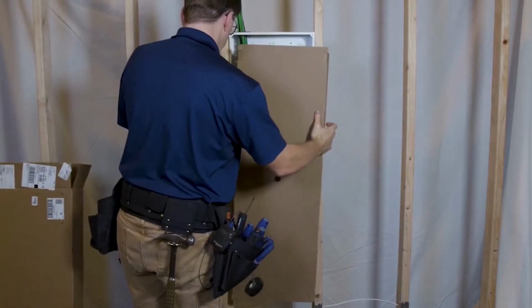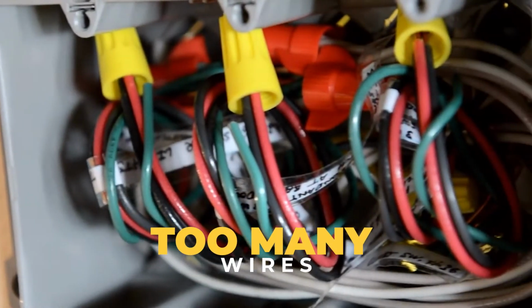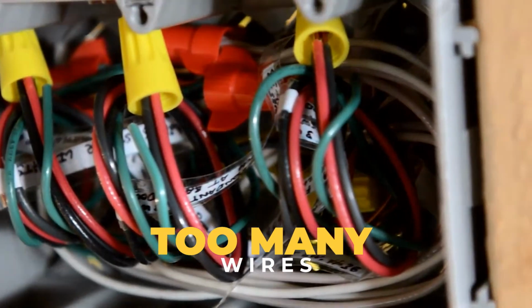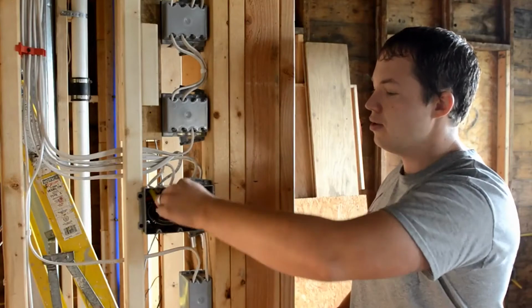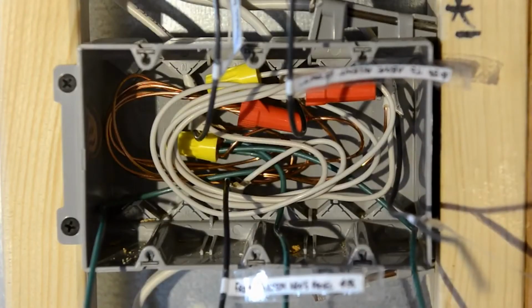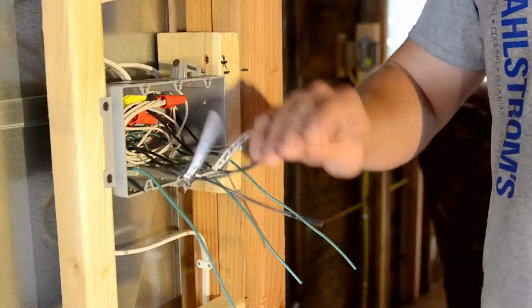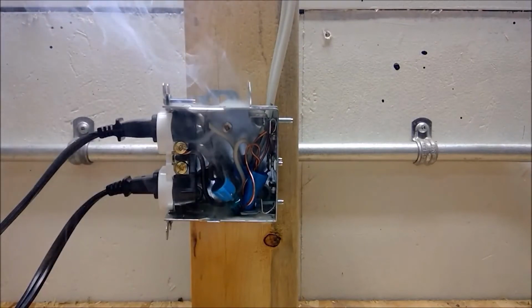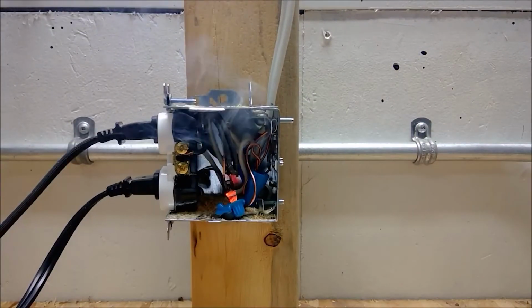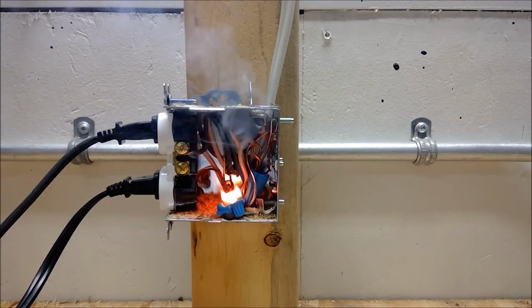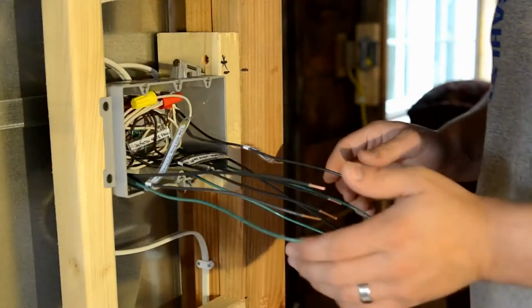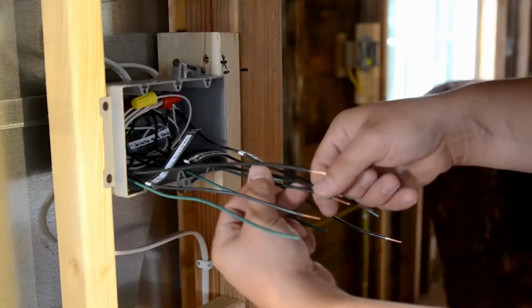Too many wires. When it comes to wiring errors, putting too many wires in an outlet box is one of the most typical ones committed by those without electrical work certificates. When there are too many wires in a box, the insulation around the area may begin to melt due to the wire's excessive heat. Naturally, a fire could start as a result of this. If an outlet box isn't large enough to accept all the cables, you'll need to use a larger box and a plate. A plaster ring is what this is called.